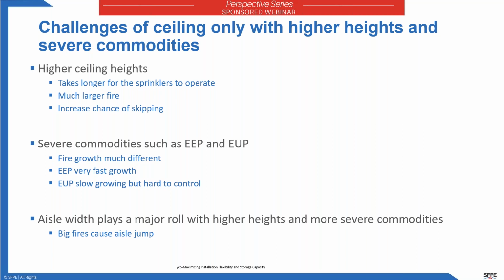The approvals, as I showed you, have different aisle widths, and it's a lot more challenging to have successful ceiling-only protection at those higher ceiling heights because it takes longer for the sprinklers to operate, which means there's a bigger fire to deal with, and we have an increased chance of skipping. Skipping is a phenomenon where a spraying sprinkler will discharge its water, and the water somehow gets negatively impacted by the fire plume and starts wetting the surrounding sprinklers and either delays or prevents the surrounding sprinklers from operating. And when skipping occurs, the chances of having a successful fire test are very low. And the higher the ceiling heights, the increased chances of skipping.